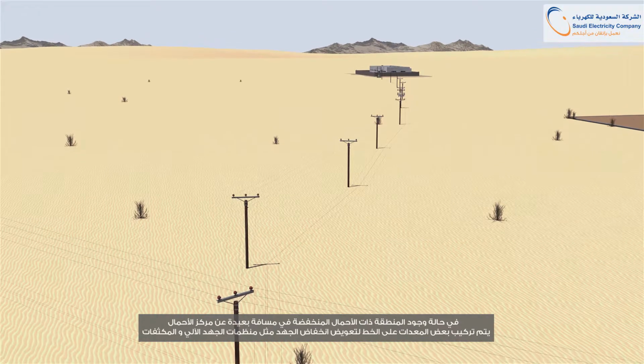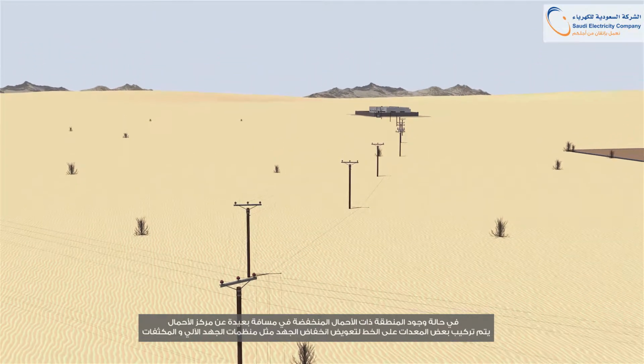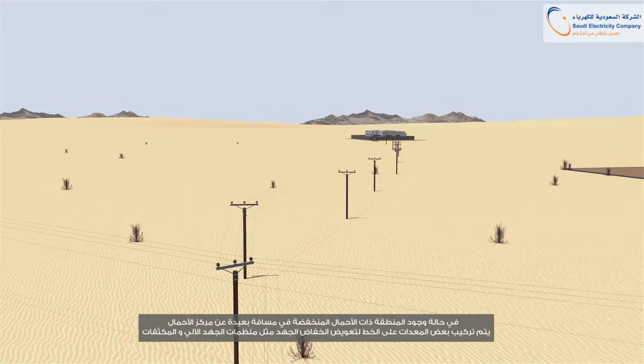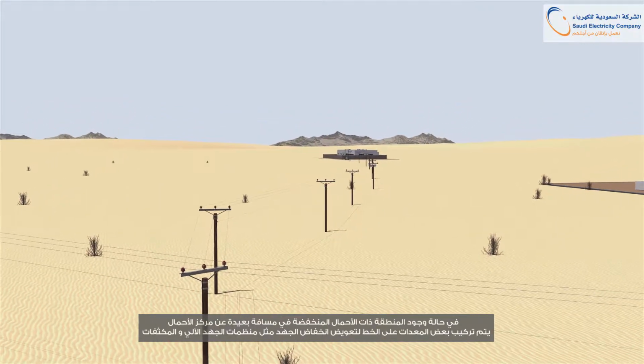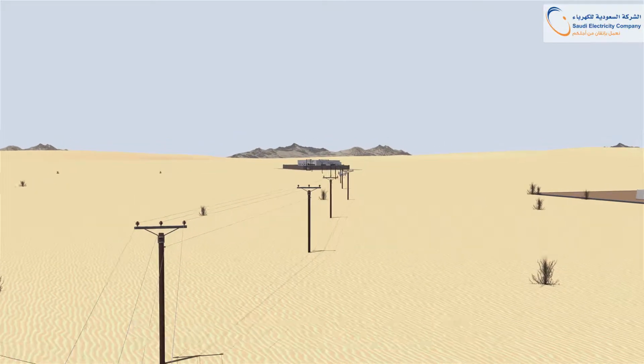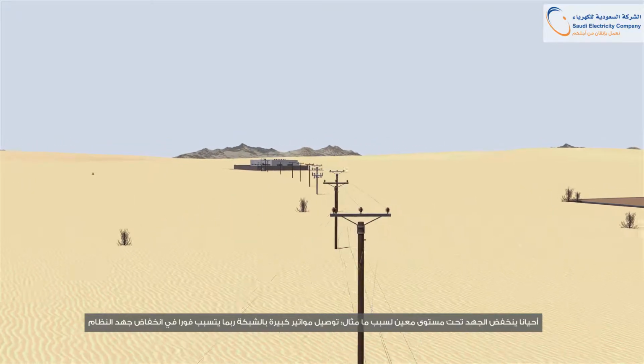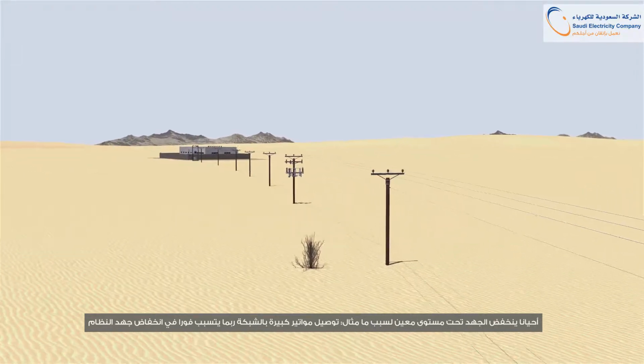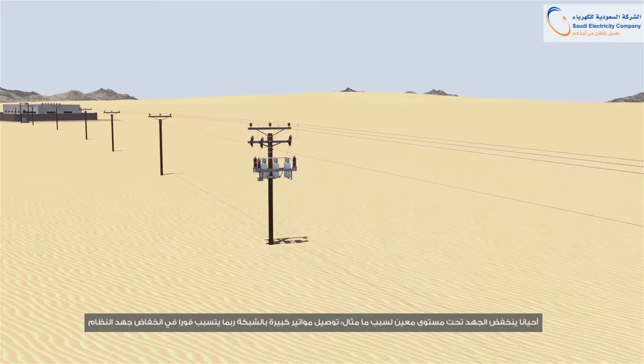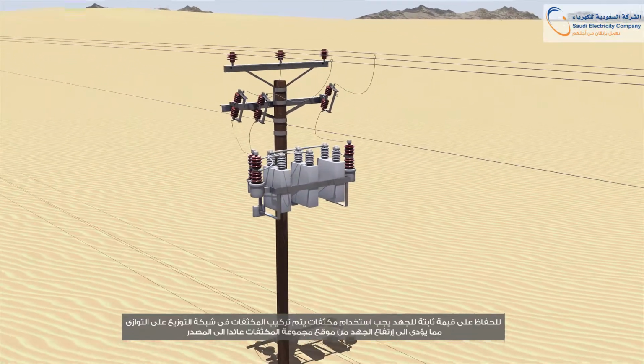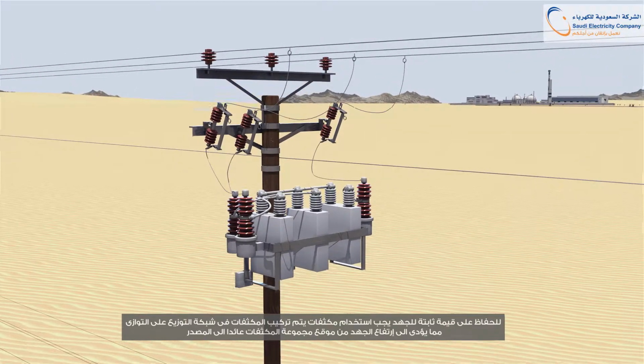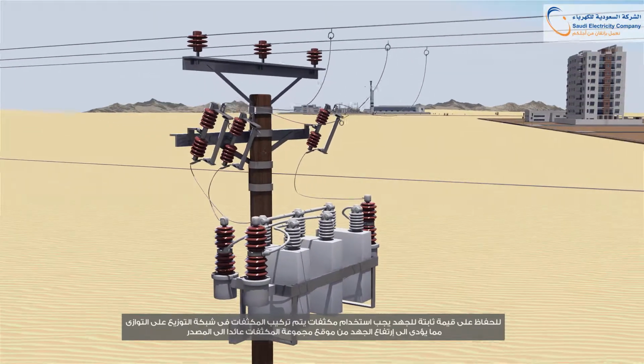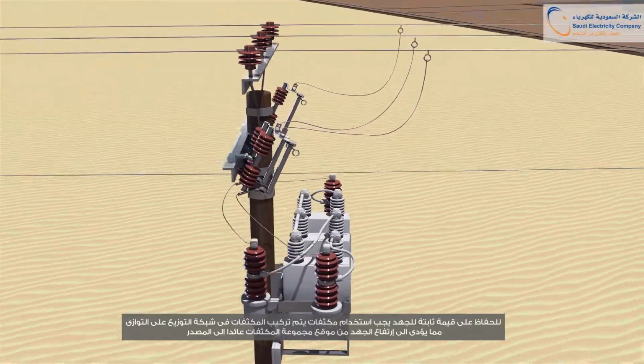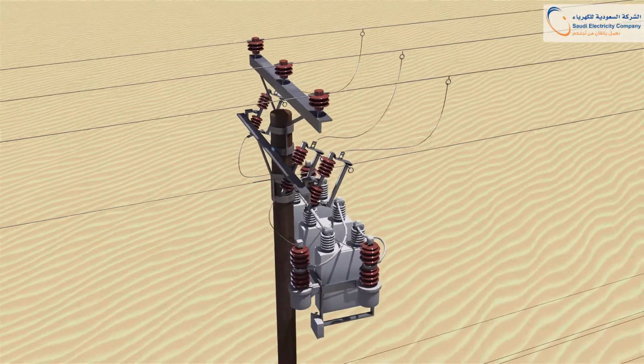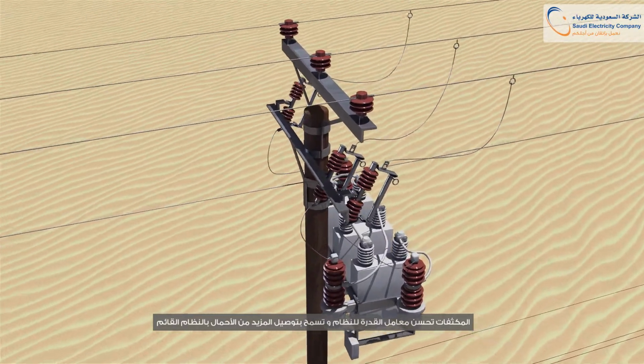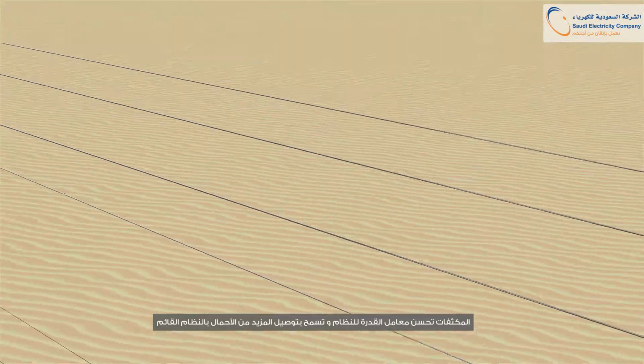In case the area with low loads is so far from the load center, there is some equipment installed on the line to compensate the voltage drop, such as automatic voltage regulators and capacitors. The voltage on a circuit may fall below a specified level for some reasons, such as connecting large motors to the system, which causes a momentary drop in the system voltage. To maintain line voltage at a constant value, capacitors are used. Shunt capacitors installed in a distribution system will cause a voltage rise from the capacitor bank location back to the source. Capacitors improve the power factor for the system and allow more load to be connected to the existing system.